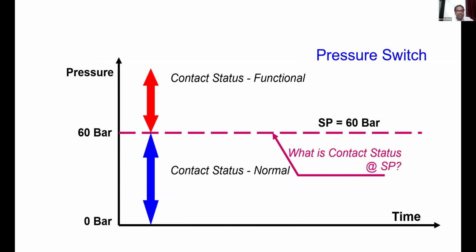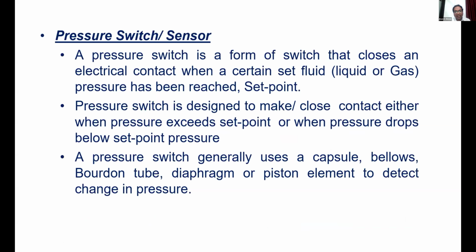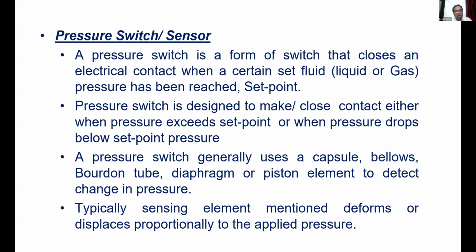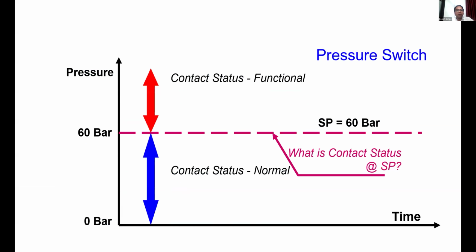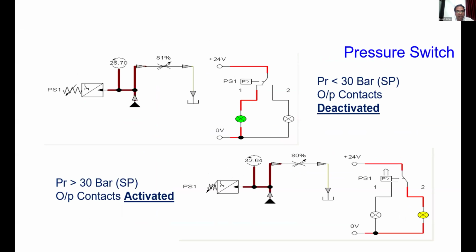Now see here, in the second situation, if the set point is 60 bar, how exactly will the pressure sensor work? Once the 60 bar pressure is reached, its contacts will change. It means, for example, I want a system to be on when I achieve 60 bar pressure. At that time, the contacts will change from normally closed to normally open. Here I have shown it with the help of a diagram.